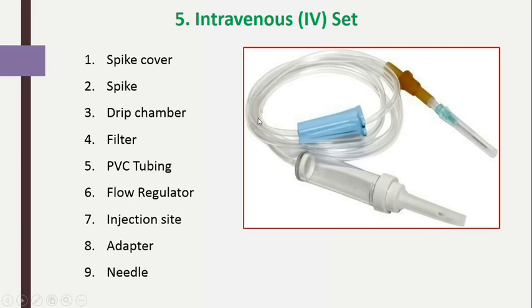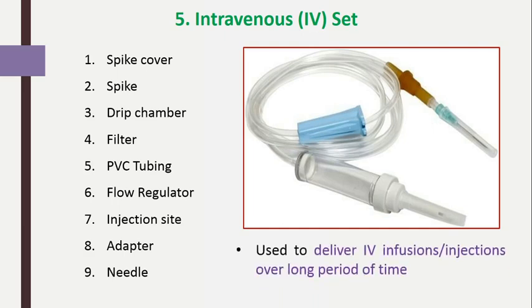The main use of this IV set is to introduce large volume parenterals. It is used to deliver IV infusions, that is intravenous infusions, or injections over a long period of time. Some requirements are needed for an IV set. It should be sterile and non-pyrogenic. Also, it should be free from particulate matter, and it should be easy to handle.